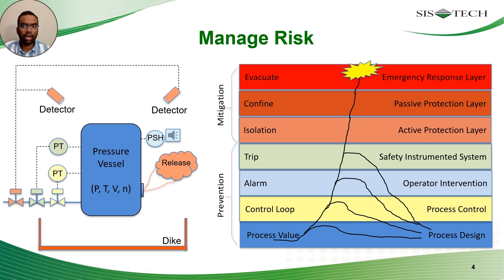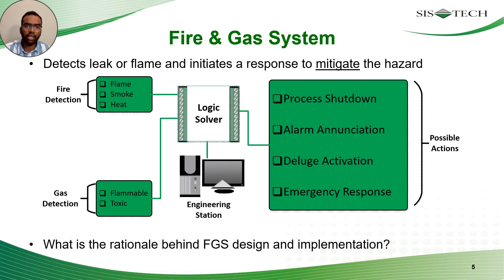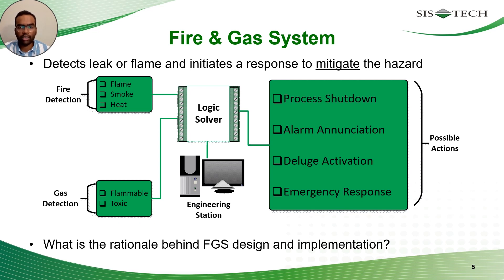Detection and action of this system is a complex problem statement to solve, and we will look into those aspects. FGS basically detects a leak or flame and initiates a response to mitigate the hazard. It provides continuous monitoring of abnormal situations like flammable or toxic gas releases within the facility. The system is designed to provide early warning after loss of primary containment to avoid further escalation. The detection hardware might be highly reliable, but there is still a likelihood that it may never detect the gas release or fire — so relying solely on hardware doesn't guarantee the effectiveness of an FGS.